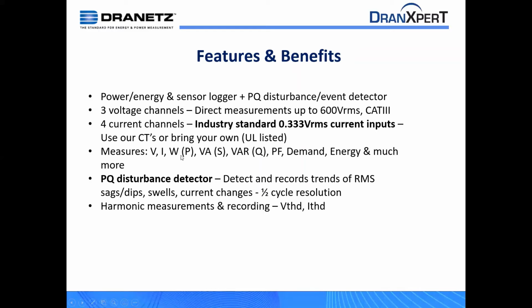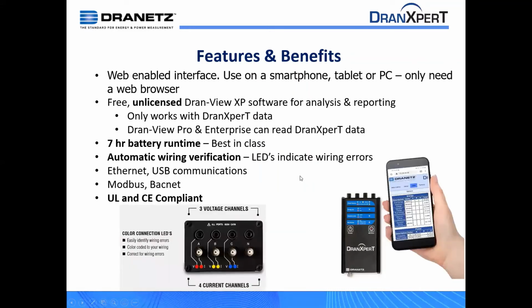Of course, we measure volts, amps, watts, VA, VARs, power factor, all the traditional energy parameters, as well as the PQ disturbance detector. Again, you'll see a trend of RMS events such as sags/dips, which are the same thing, swells, and changes in current. Again, changes in current are current high, current low if you enable it. And that is all to a half an AC cycle resolution. You get harmonics and other parameters in parallel with that.